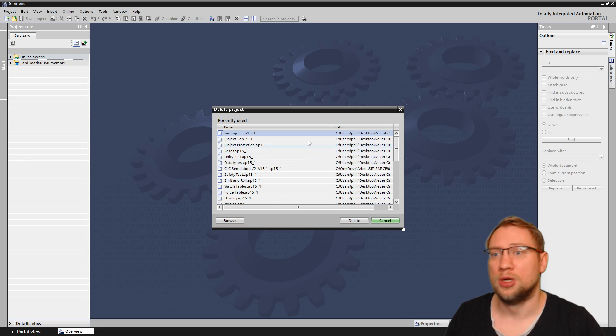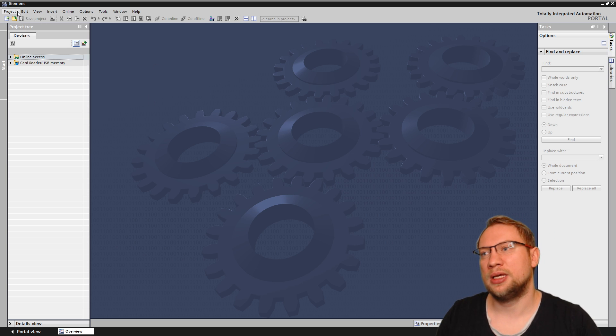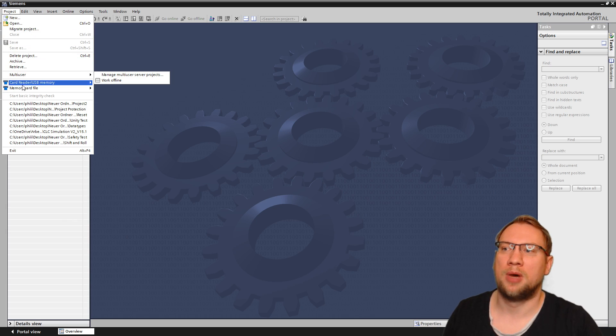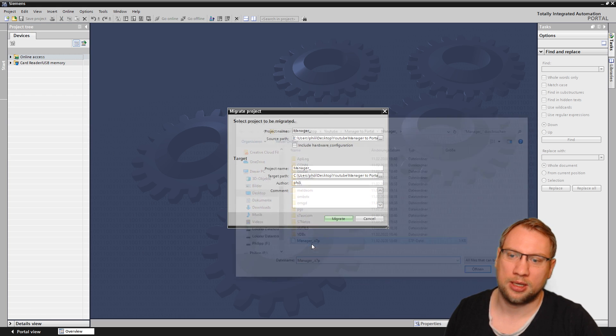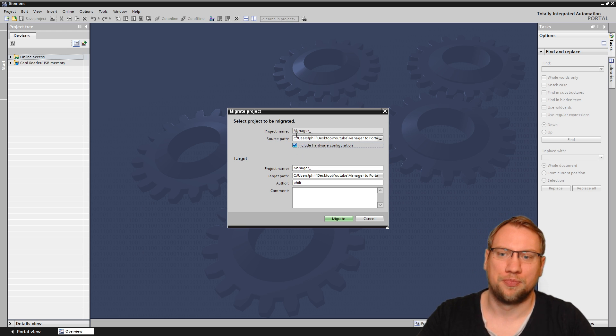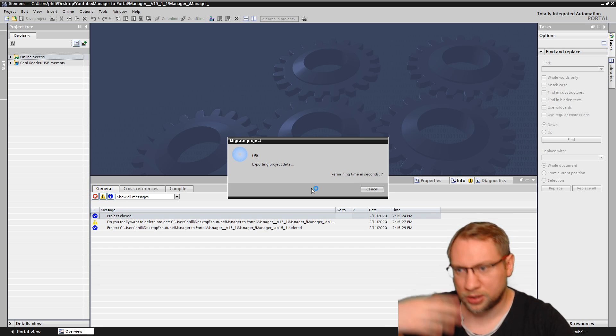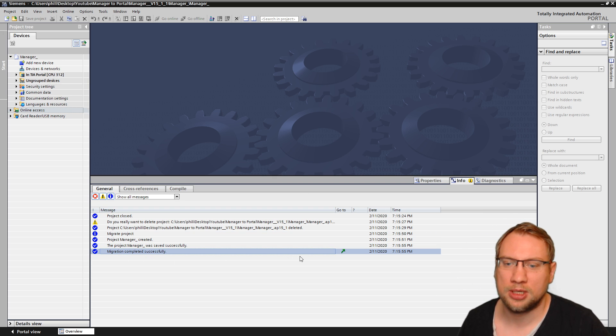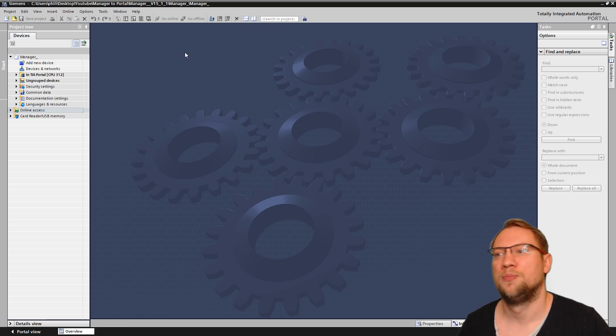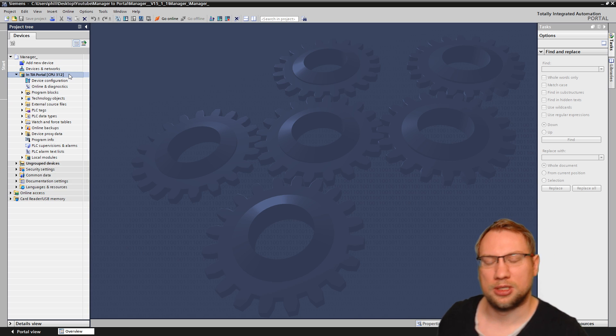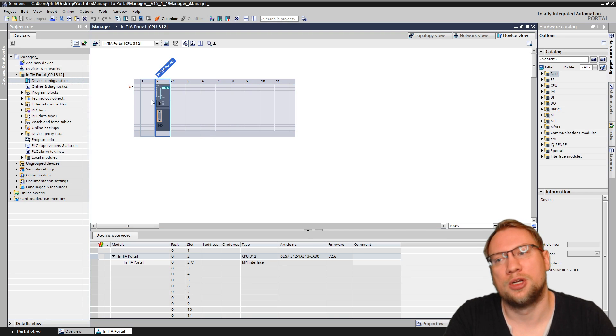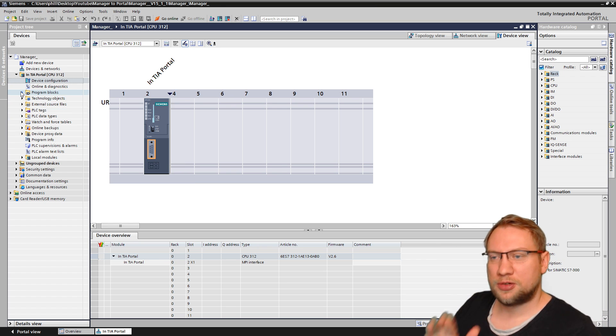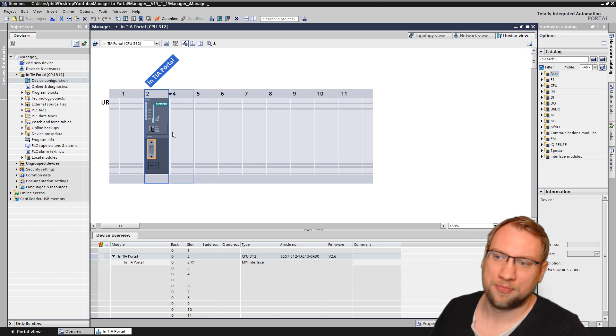The next scenario: we can migrate either in Portal View via 'Migrate Project,' or in Project View via Project > Migrate. I choose the same project again, but this time I will check 'Include hardware configuration' and click Migrate. My PC is pretty fast and the project is pretty small — migration completed successfully, no warnings at all. Now the PLC is here in TIA Portal — that's the name I gave it in SIMATIC Manager — and if I go to hardware configuration, it is all there.